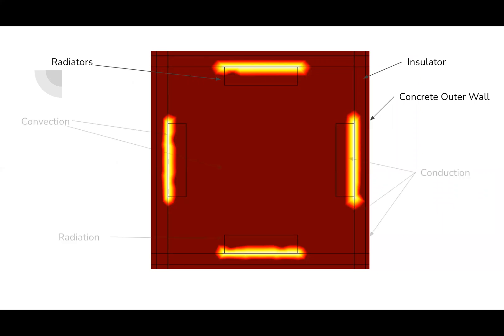Now I want to mention the heat transfer that will be happening in this simulation. At the base of the radiator, there is steam, which will be convecting heat to the radiator steel. Then there will be conduction through the radiator, and also conduction through the insulation and maybe even the concrete if the heat loss reaches that far. Then we also have radiation from the outside of the radiator to the room, followed by convection throughout the air in the room.